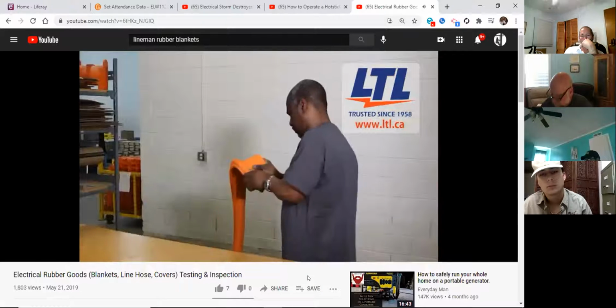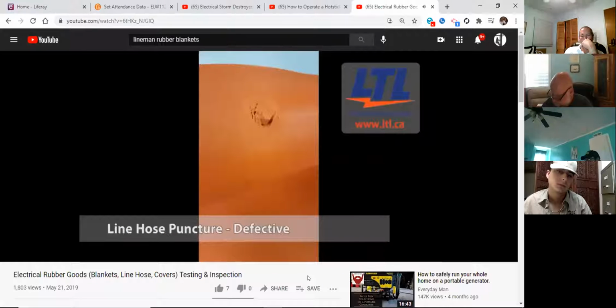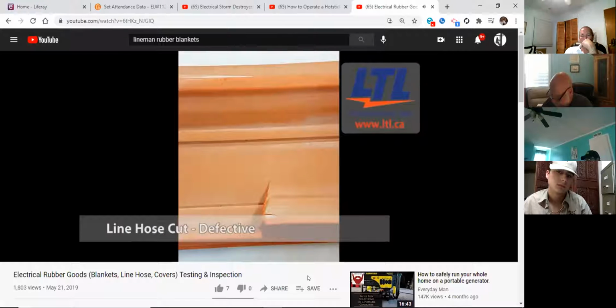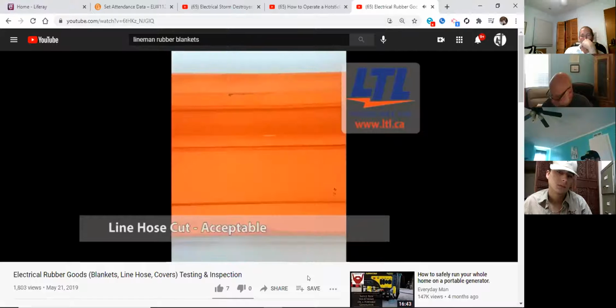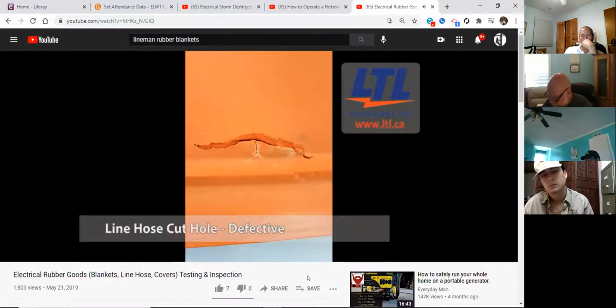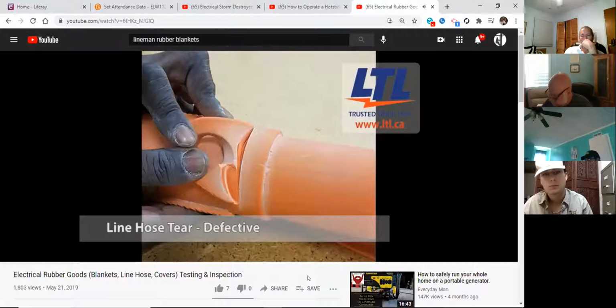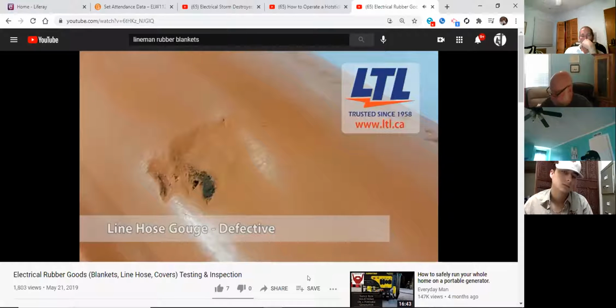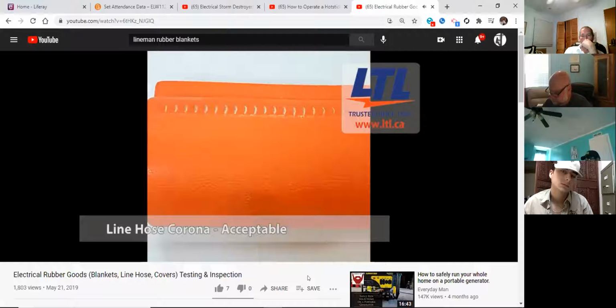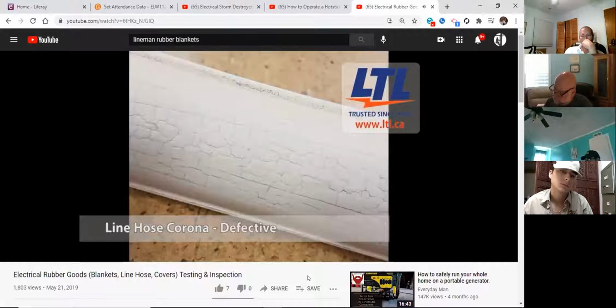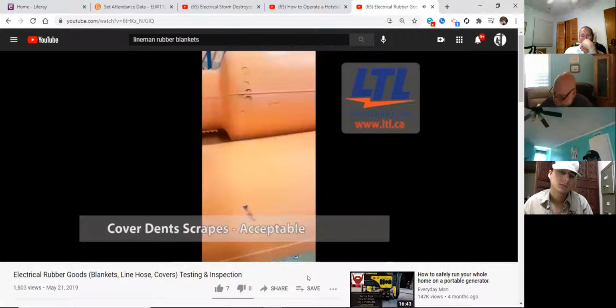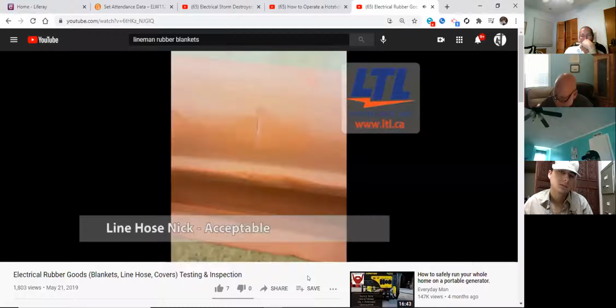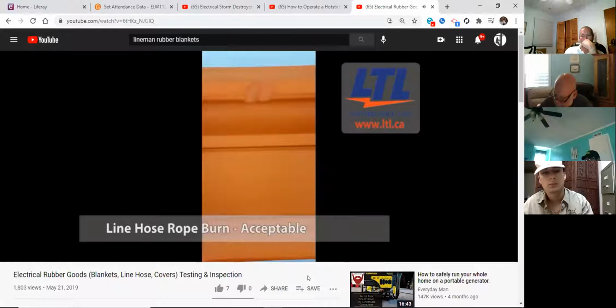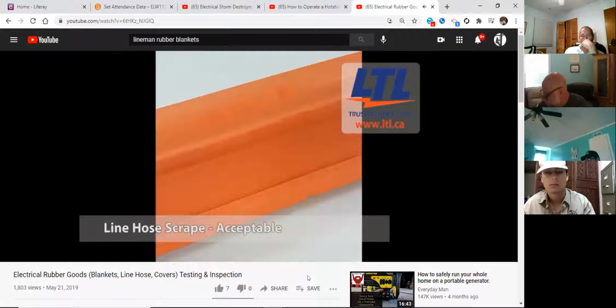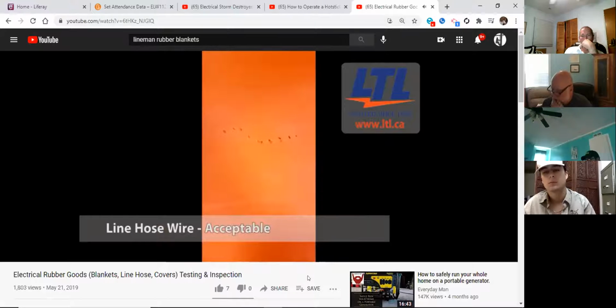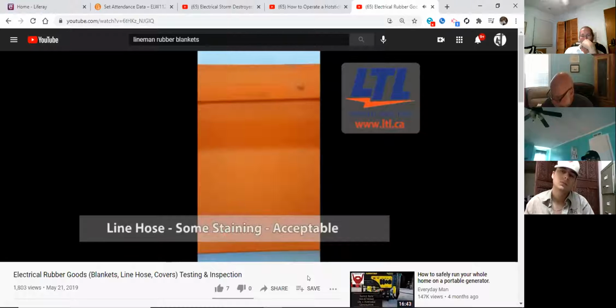Insulating line hose and covers are inspected for punctures, cuts, severe ozone cutting, holes other than factory produced openings on the top sides or lips of the line hose or covers, tears and punctures, serious cuts, and rope or wire burns that extend more than one third the depth of the thickness of the rubber per ASTM F478 section 11.7.1. Also check for texture changes, swelling, softening, hardening, and becoming sticky or inelastic, and other defects that damage the insulating properties and would adversely affect performance.